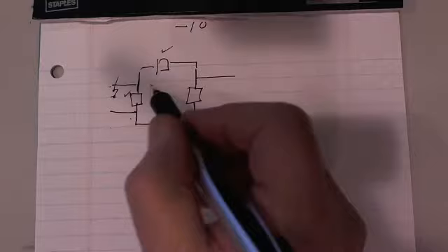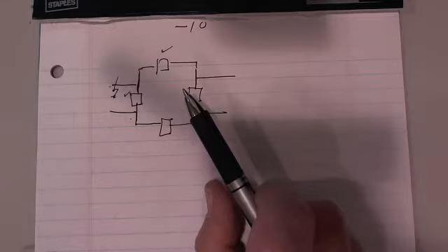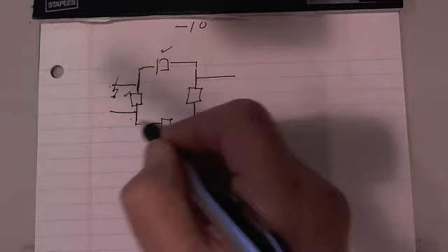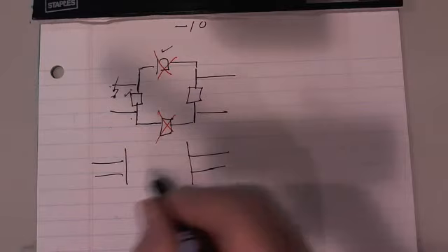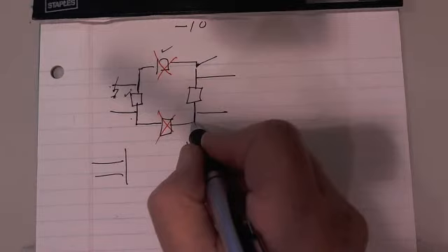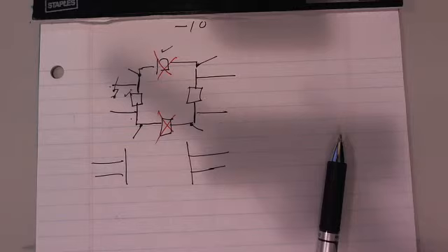You can see it in the beginning chapter of our book on power flow, where we talk about ring buses, and breaker and a half, and so forth and so forth. If you split the bus, so suppose we indicate that this breaker and this breaker is open, well, then we have essentially buses that look like this without drawing the breakers, that I've split it. Well, if that's the case, then I have to have a GPS measurement here, and a GPS measurement on every single what we call bus section inside that ring bus. Four of them. I gotta have four of them hooked up. Maybe they'll get there someday, but they're not there by now.